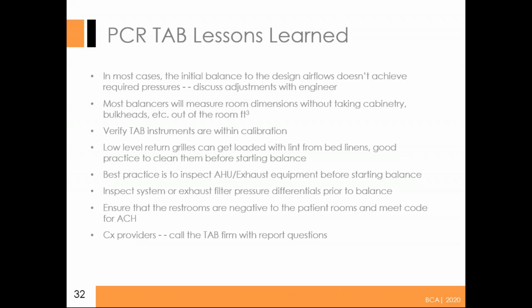But we've got to remember too, a lot of these rooms today, they can be positive or negative with a flip of the switch, or in the unoccupied mode. So you could be setting these rooms up in a multiple scenario deal. I know I don't like them. I like to see, myself, it just gets too cumbersome for the users. And the other thing too is if the users really don't understand those rooms, they're putting infectious patients in and they're not properly setting those pressure monitors for positive or negative. I've seen that happen. But outside of that, that's pretty much all we have right here.